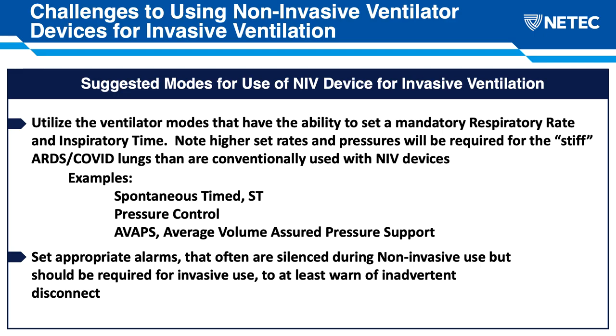that would be the best. With a lot of these devices, the alarms are set very low or sometimes off, because we know we have a lot of leaks when we're using them traditionally as non-invasive with a mask. So you want to make sure that those alarms are activated, so at least you know of a disconnect, since this is your total life support with these patients, utilizing it through an ET tube.